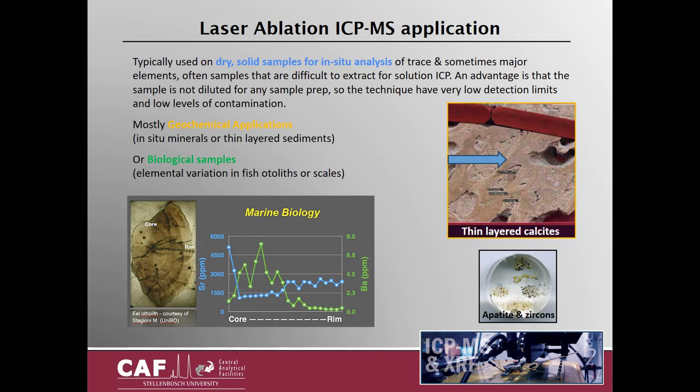Laser ablation ICP-MS is typically used on dry solid samples for in-situ analysis of trace and sometimes major elements, often on samples that are difficult to extract for solution ICP. An advantage is that the sample is not diluted for any sample prep, so the technique has very low detection limits and also low levels of contamination. Analysis is mostly done on geochemical samples such as minerals or sediments, but also on biological material such as bone, teeth, or fish otoliths. Analysis is typically done at spot sizes from 10 to 100 microns, but continuous line scans at the same diameter can also be applied.